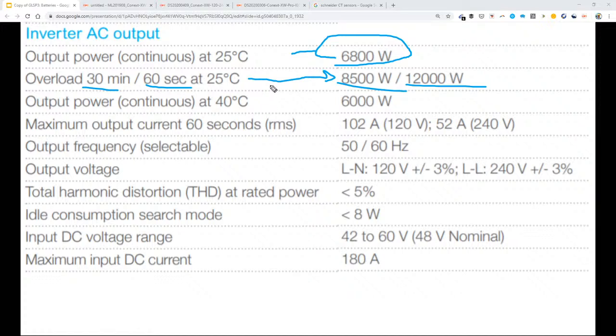What I would have to say about surge loads in a house is they usually run for 8 to 10 to 12 minutes in that range, like an air conditioning unit or an electric tank water heater. They don't run for 30 seconds and then stop. Most go longer than 60 seconds. So I wouldn't really take into account this maximum surge load capacity when you're just trying to say, okay, well, if we exceed our power, what happens? If you exceed your power slightly on a battery inverter, it can take it. But if you go over what it can output safely within a minute, it shuts off. So if you overload a battery inverter, it will turn itself off, because the conductors wired up to that battery inverter are only rated for its continuous output rating. So it's not an inverter that can do higher output sustained for very long.